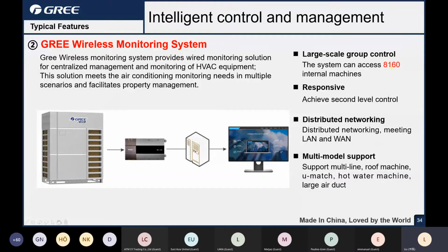Okay, so the expansibility is very good, and also the response, because for the laptops you need a gateway and a cable to connect with the VRF. So you know the control precision is about a millisecond. And next one is the distributed networking. You can use a LAN network or WAN network, depending on your design. And for the unit models, not only VRF, but also the rooftop, UMatch, hot water, and air duct, large air duct, all of these units can use the wireless monitoring software. Okay, that's the first solution.